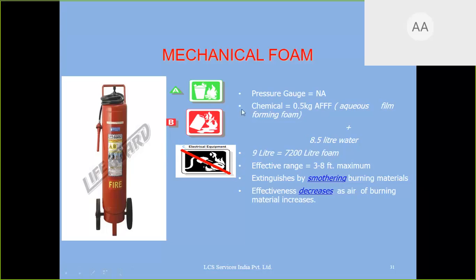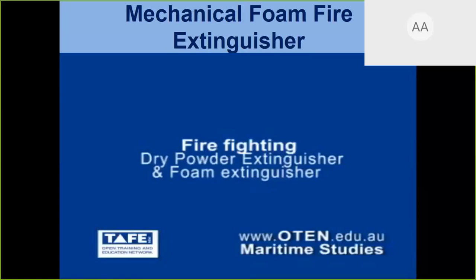I will show you in this slide how it can be. There is no pressure gauge in this. The chemical is this. 9 liters capacity is there. Effective range is this. And the expansion ratio is so high that this 9 liters will become 7200 liters of foam. From this 9 liters, I get 7200 liters of foam when it is mixed with air. Right? So this is a video of the mechanical foam.